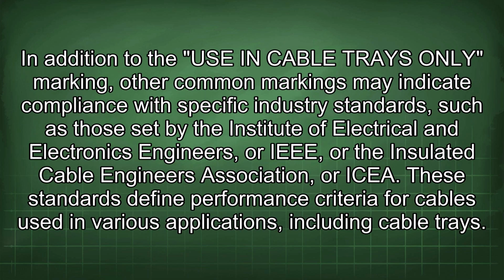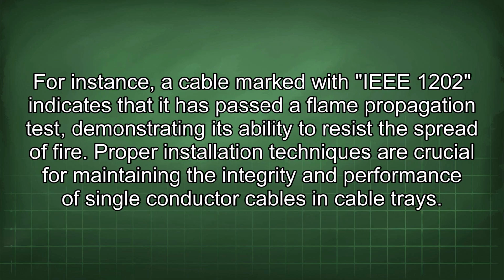In addition to the "use in cable trays only" marking, other common markings may indicate compliance with specific industry standards, such as those set by the Institute of Electrical and Electronics Engineers, or IEEE, or the Insulated Cable Engineers Association, or ICEA. These standards define performance criteria for cables used in various applications, including cable trays. For instance, a cable marked with IEEE 1202 indicates that it has passed a flame propagation test, demonstrating its ability to resist the spread of fire.